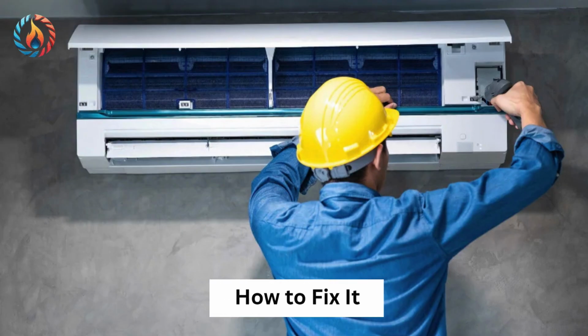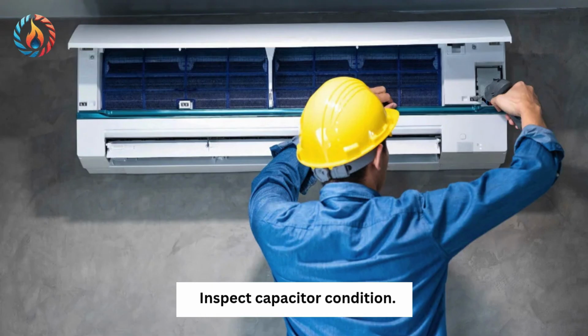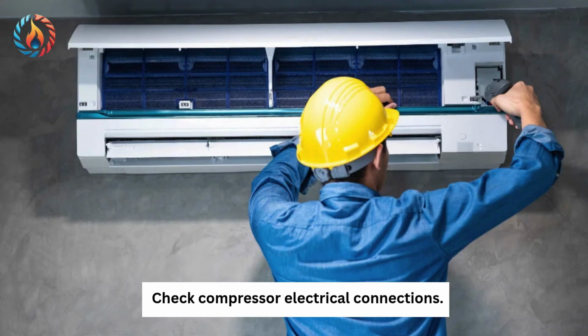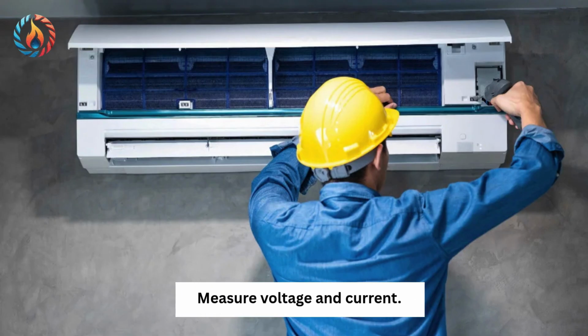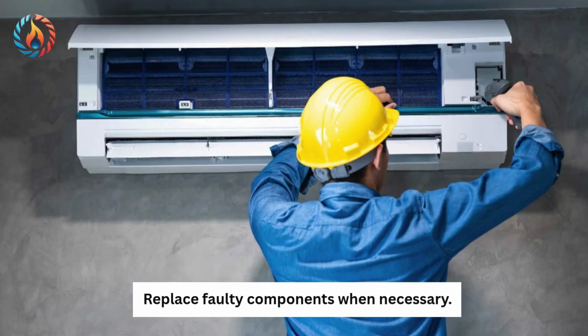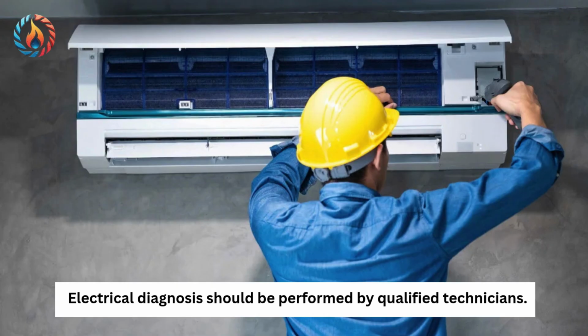How to fix it? Inspect capacitor condition. Check compressor electrical connections. Measure voltage and current. Replace faulty components when necessary. Electrical diagnosis should be performed by qualified technicians.